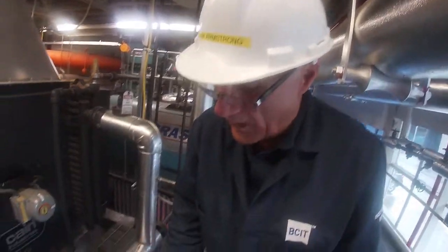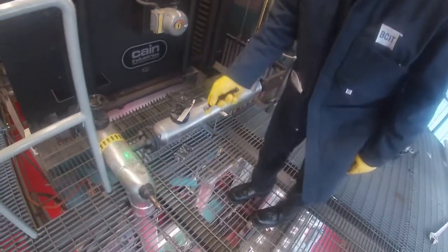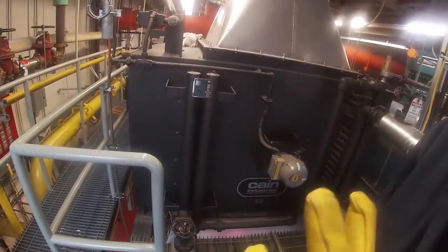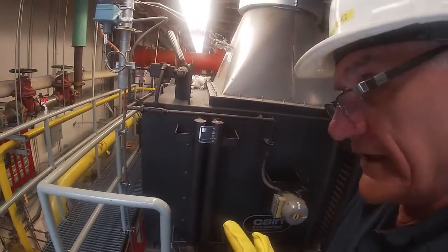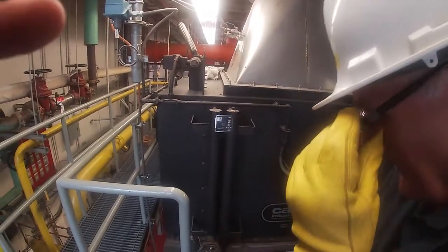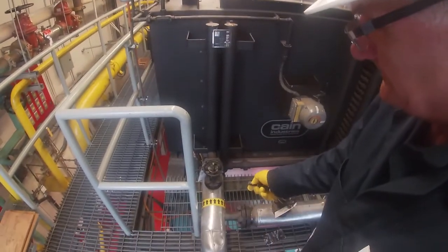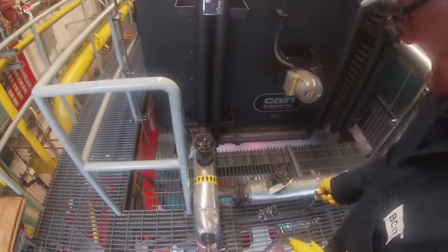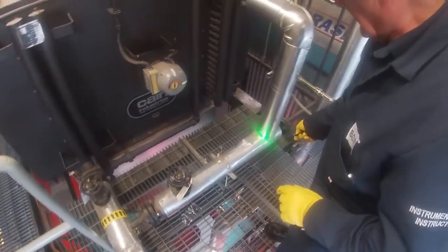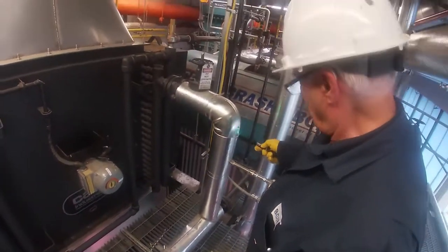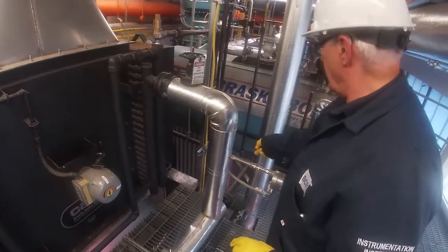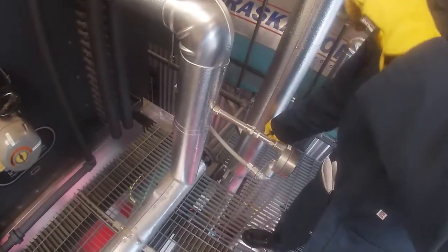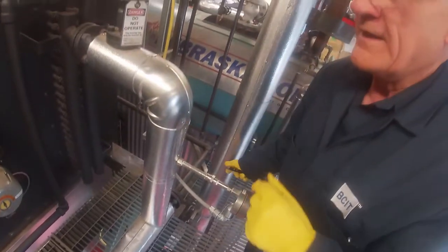Now, the water's coming out of the feed water valve here. The economizer can run in bypass, two different modes. Bypass of the liquid or bypass of the gases. If you're bypassing the liquid, you would close the inlet valve and open this bypass valve, and then from here it would come up and go straight across, and this line coming out the end of this sort of header is going to the boiler drum at the front.